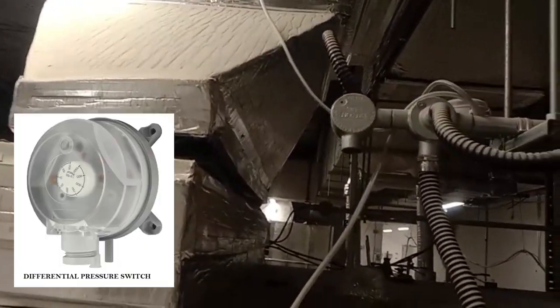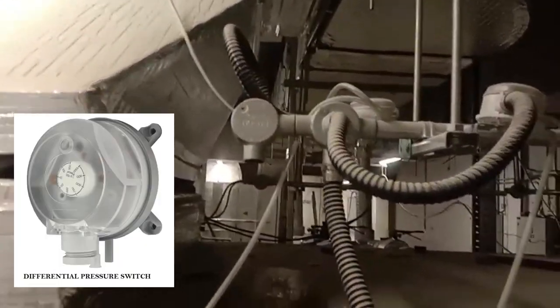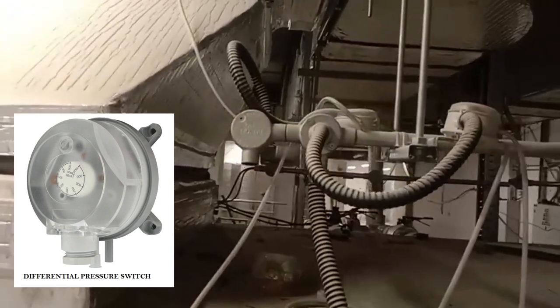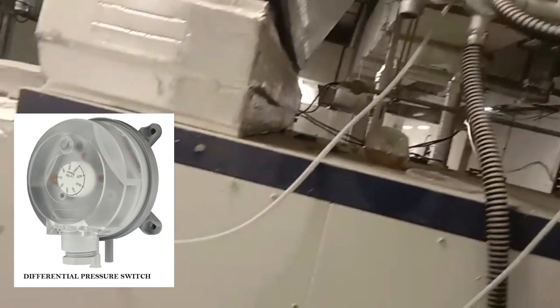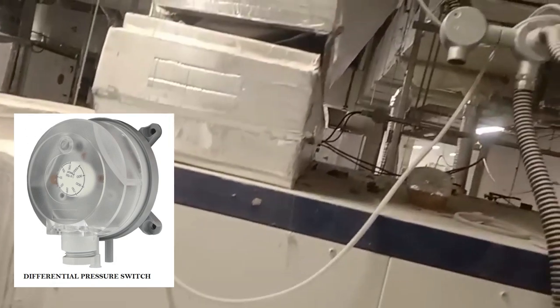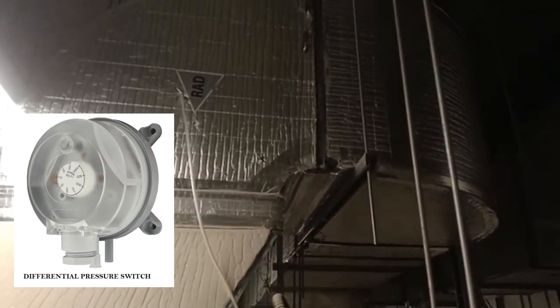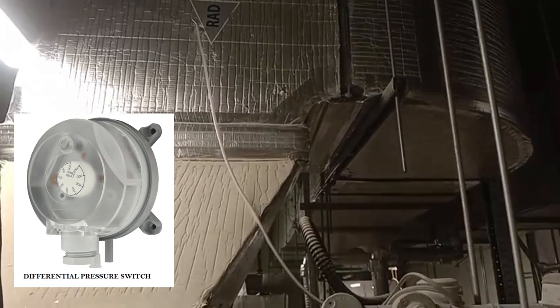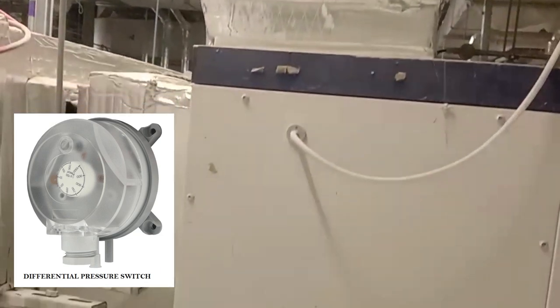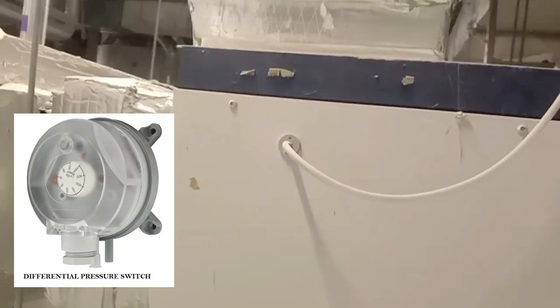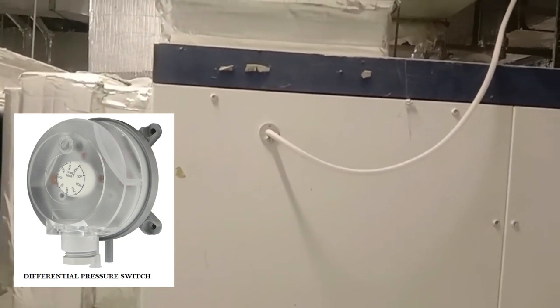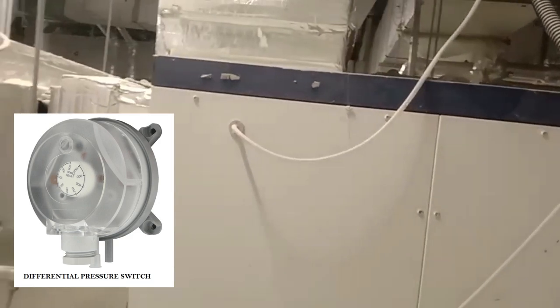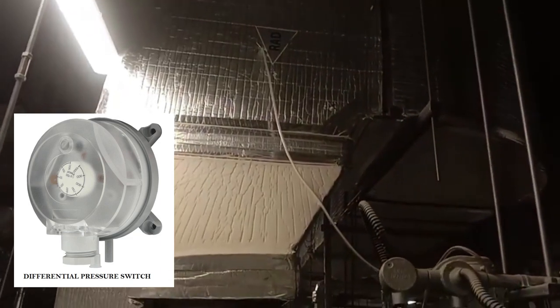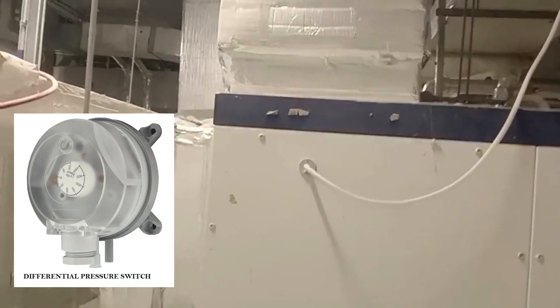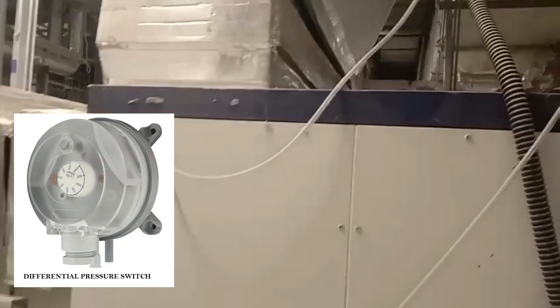The same way also for the return air duct, we also have our differential pressure switches, which are also installed. As you can see right up, and then we have also connected from the return part of the duct, as you can see. And then we have it also connected after the damper. Once the damper is open, it measures the pressure difference between the air which is leaving from the building, coming back inside the AHU. It measures the pressure difference.